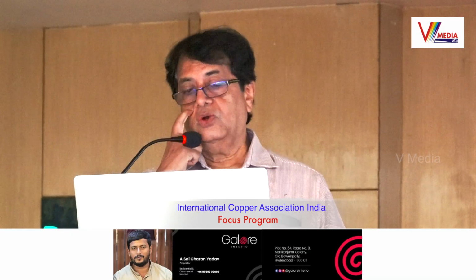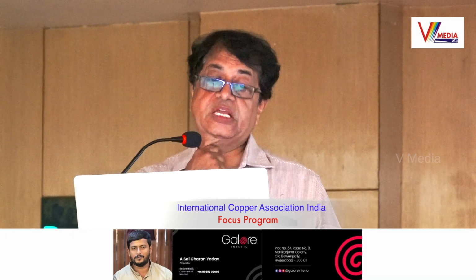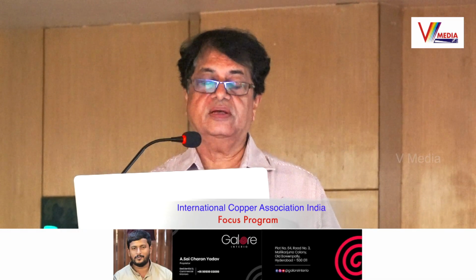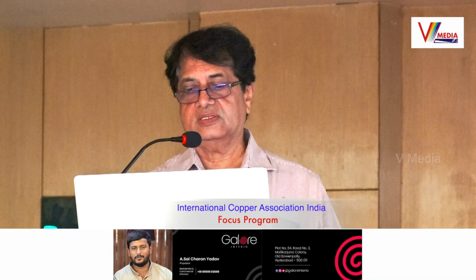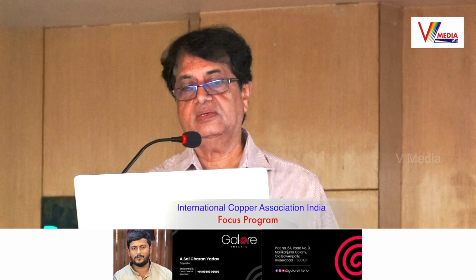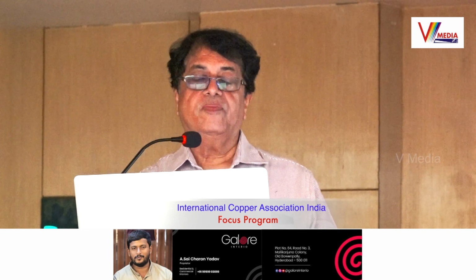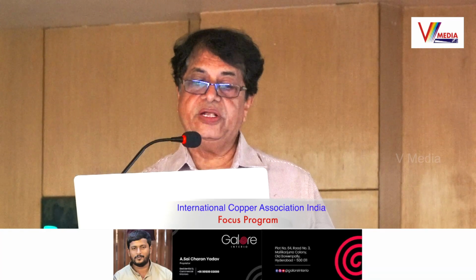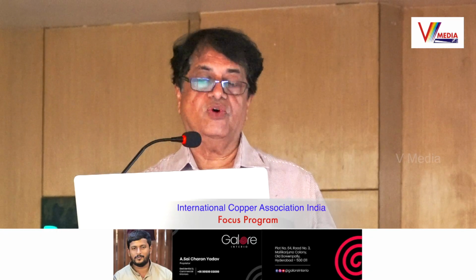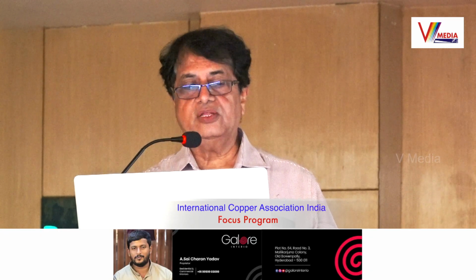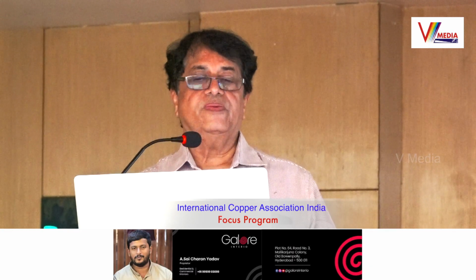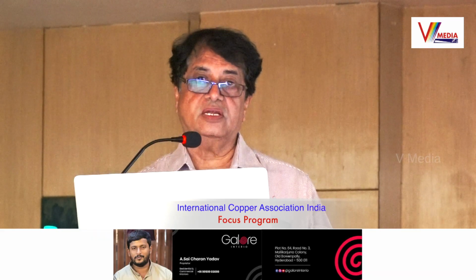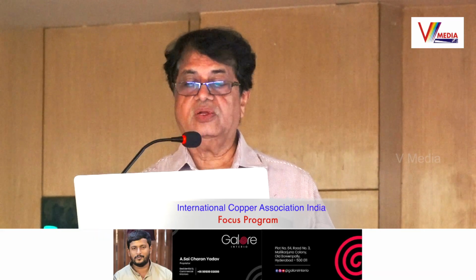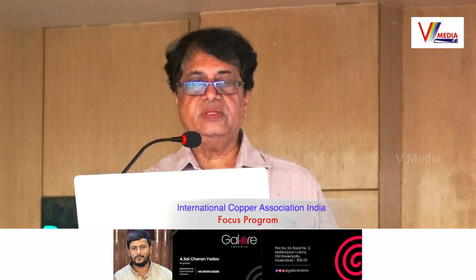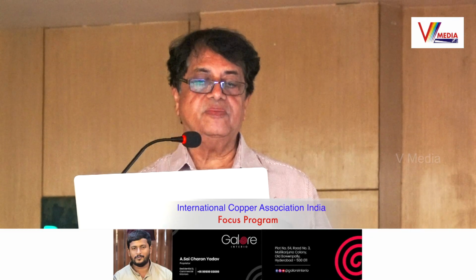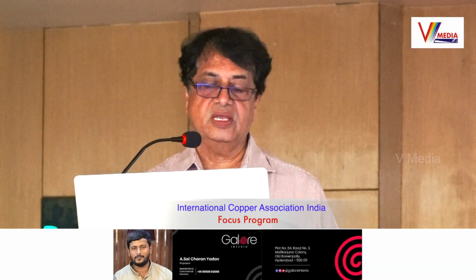In the National Electrical Code, building code and the standards also, some requirements are given in respect of wet areas like bathrooms and shower areas. In bathroom and shower areas, different conditions apply for the electrical installations. There are different zones which have been defined in the regulations and the code, and as per those zones, the risk of fire is categorized. And depending on the risk, there are different requirements in respect of the walls, wall thicknesses also, and clearance to be maintained. So there has to be again coordination between the designer and the architect. If sufficient clearances are not achievable, then the electrical consultant may have to use a low voltage system, a 12 volt system, or even a 25 volt system. So coordination between the electrical designer and architect is very, very important at each and every point at the planning stage. Again, I am telling you, before you plan and make your final drawings, it is important.